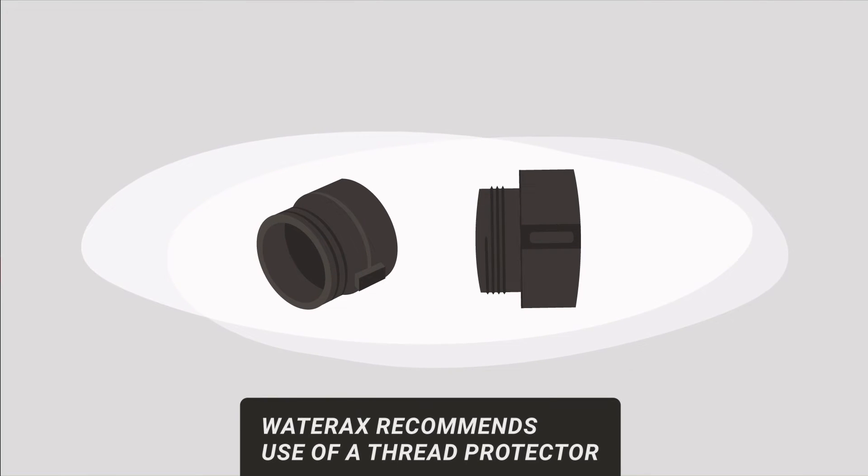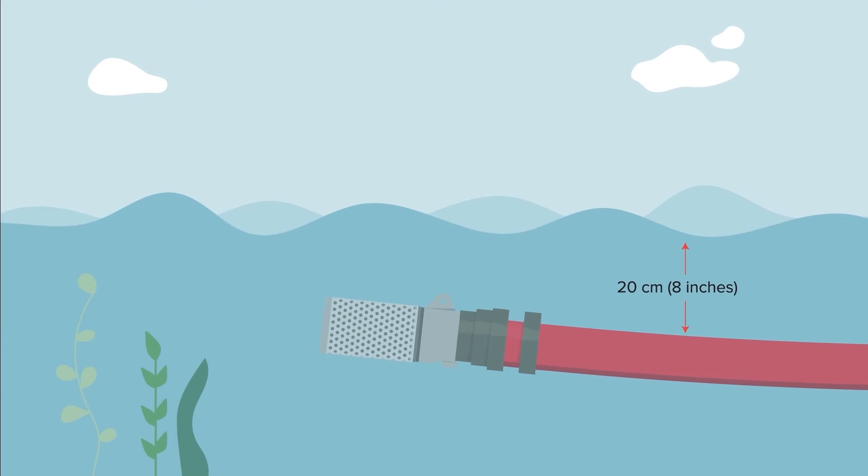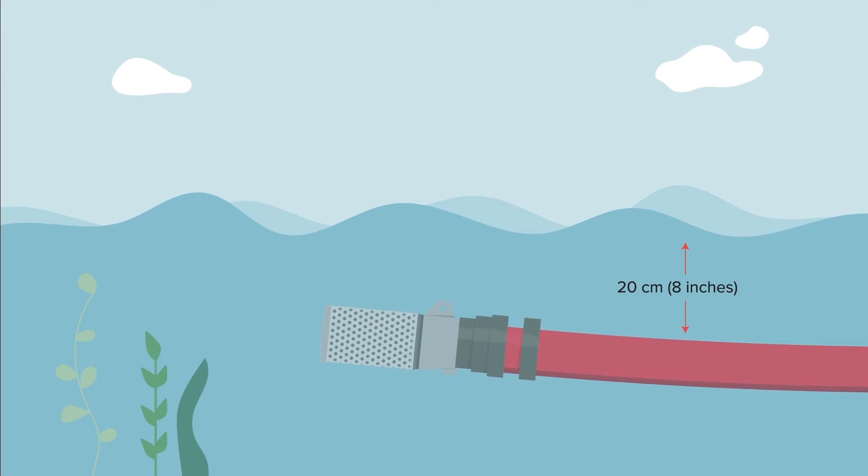Cross threading can damage the connection and create air leaks that lead to air locks and potential pump end seizure. WATERAX recommends the use of a thread protector to protect the pump end threads against any damage. Allowing at least 20 centimeters of water above the foot valve will stop any air from being sucked into the pump end.